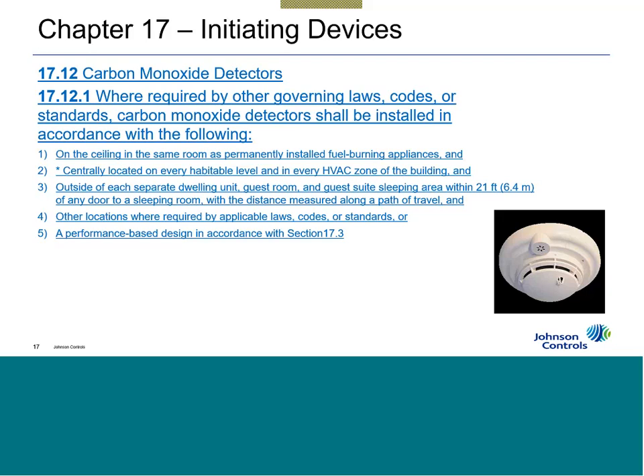So wait a minute, again, you just told me there is no spacing requirements for CO. Where did 21 feet come from? Specifically a certain number that says 21, not 20, not 15. Whenever I see a number like that come up in our codes, I always like to investigate why it is used and where it came from. Well, if you look down here in the bottom right corner, this is an example of a Johnson Controls Autocall carbon monoxide detector. The detector here is built into the base. It's a cartridge, and pretty much all of your systems people, Honeywell, Siemens, Hochiki, Bosch, we all put carbon monoxide devices in conjunction with our smoke detectors.